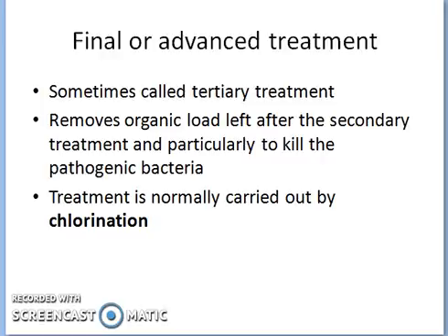Now coming to the final or advanced treatment. This treatment is sometimes called the tertiary treatment and consists in removing the organic load left after the secondary treatment and particularly to kill the pathogenic bacteria. This treatment, which is normally carried out by chlorination, is generally not carried out for disposal of sewage in water, but is carried out while using the river stream for collecting water for reuse of water supplies. And it removes the organic load left after the secondary treatment, particularly to kill the pathogenic bacteria.